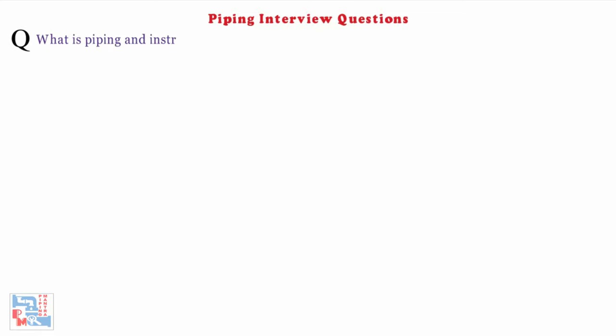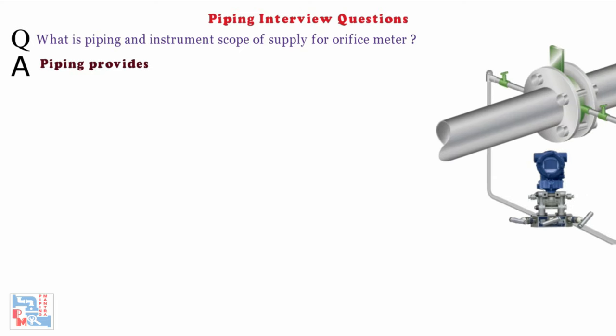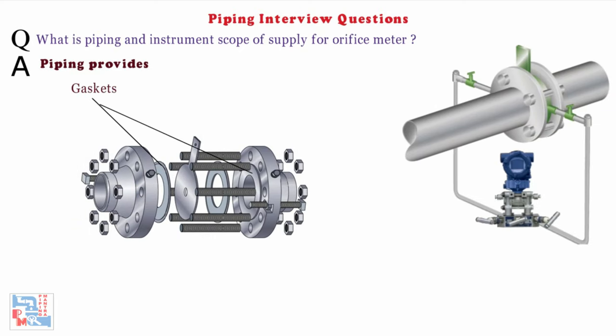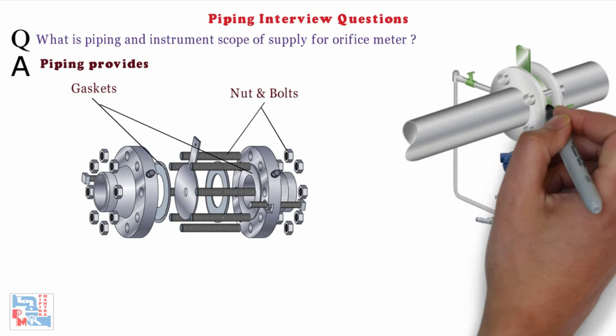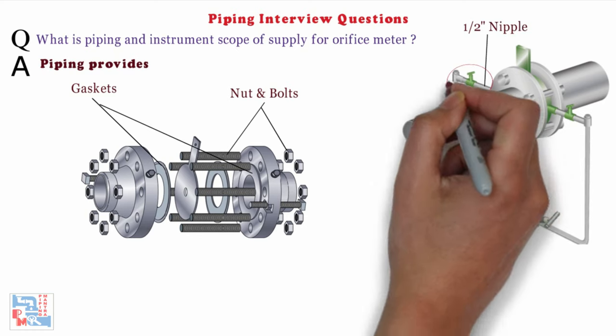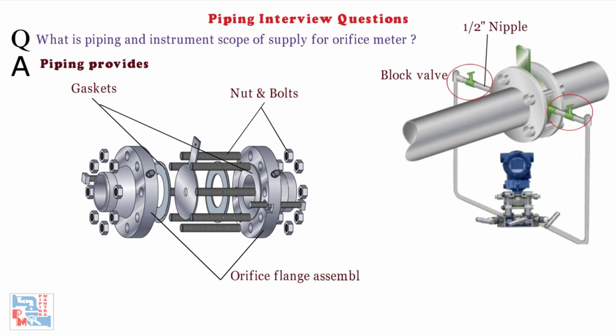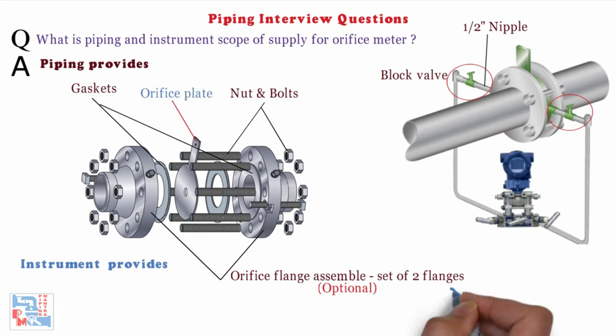What is the piping and instrument scope of supply for an orifice meter? Piping provides gaskets, nut bolts, and tappings from the orifice plate — most probably a half-inch nipple with two block valves — and orifice flange assembly (a set of two flanges, optional). Instrument provides the orifice plate along with the flange assembly and tubing connection downstream of block valves up to the DP transmitter.